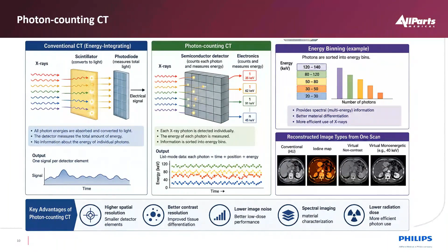So the key elements of all this are that we get higher resolution, better contrast, and lower image noise. The spectral imaging gives us better detail on what the material is. On top of that, because of the newer algorithms that enhance this data set and the lower noise in the image, we can actually reduce radiation, because we can produce fewer photons out of the X-ray tube, aka lower current going through the X-ray tube, which improves our quality of health by not getting as much X-ray. So it enhances all these functions.